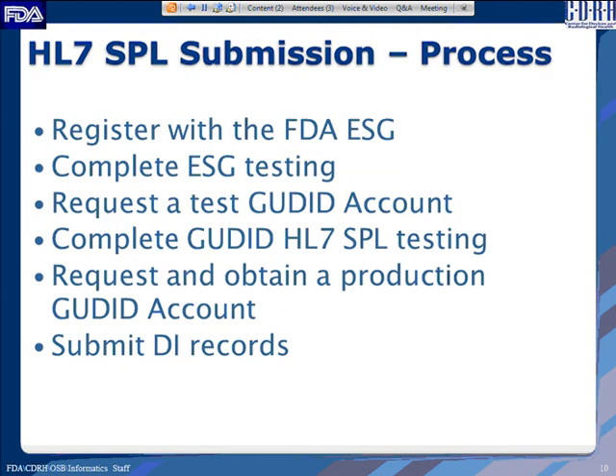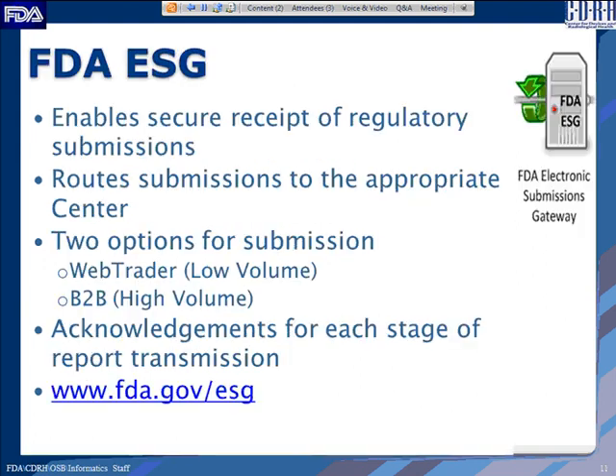The process for a labeler wanting to use the HL7 SPL submission option is: register with the FDA Electronic Submissions Gateway, complete ESG testing, then request a test GUDID account. Once testing is complete, request and obtain a production GUDID account, which enables submitting production GoodID records.